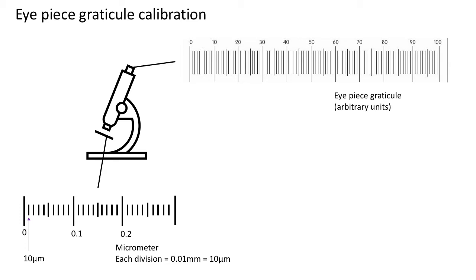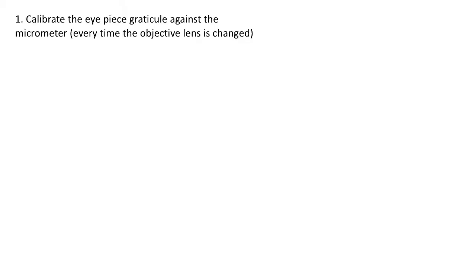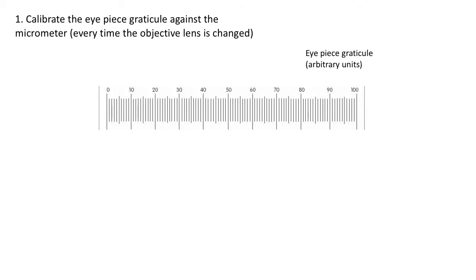Let's go through the calibration process. You need to calibrate the eyepiece every time you're using the microscope for the first time, or any time you're changing the objective lens to look at a different magnification. This has to be done every time.